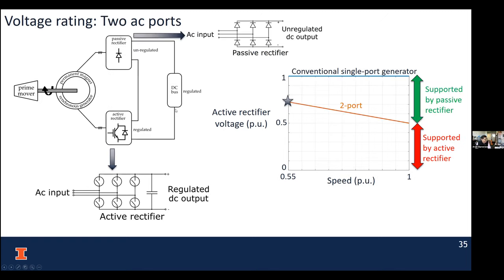Now let's bring in a two port system, one with the passive rectifier and one with the active rectifier, and see what we can do. The passive rectifier output voltage is unregulated - we have no control. So as speed goes down, the voltage at the output of the passive rectifier gradually goes down. If we have to maintain the DC bus voltage, the active rectifier voltage must increase to compensate. As you can see on the right, as we decrease generator speed, the passive rectifier voltage share goes down while the active rectifier share goes up, maintaining the DC bus voltage at one per unit. What's interesting is that the active rectifier voltage rating can be reduced from 1 to around 0.75 - you don't have to deal with one per unit voltage rating.